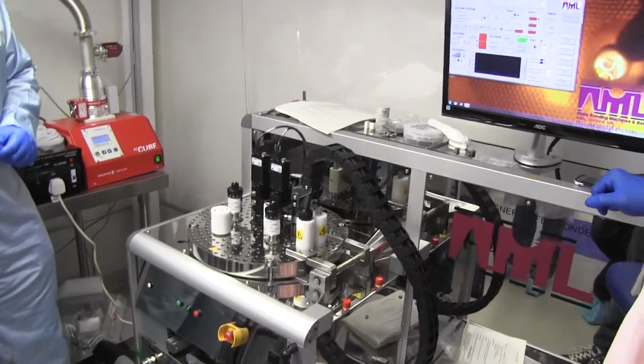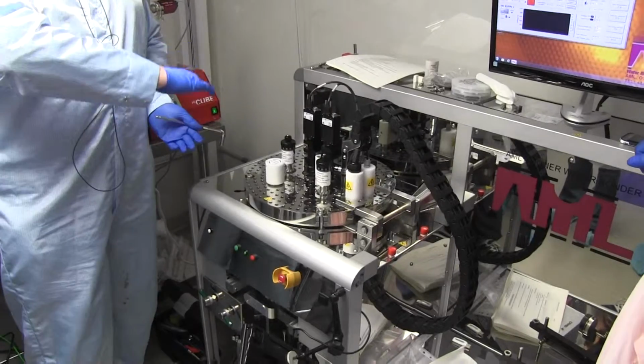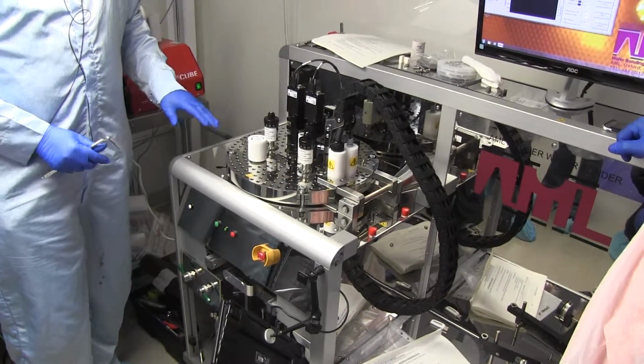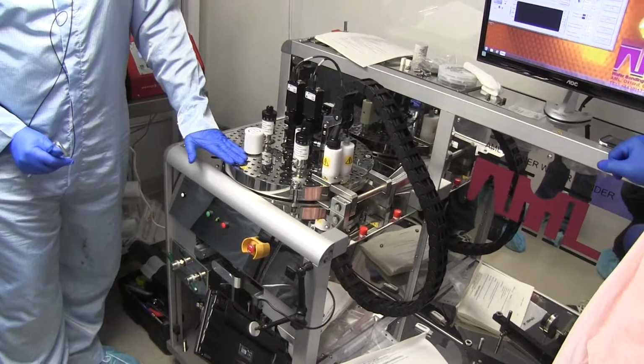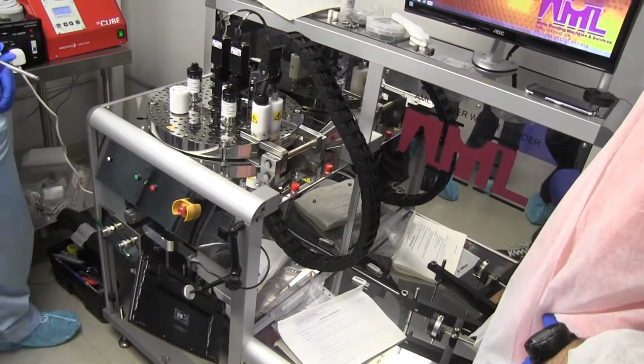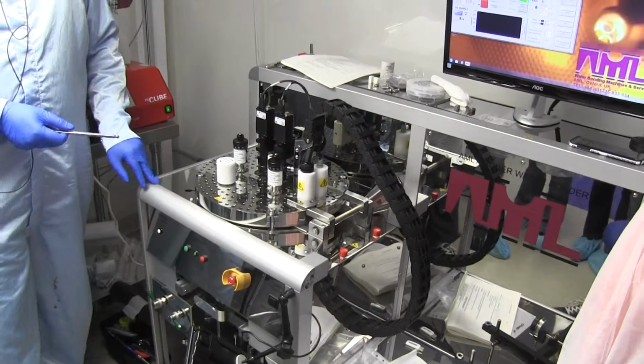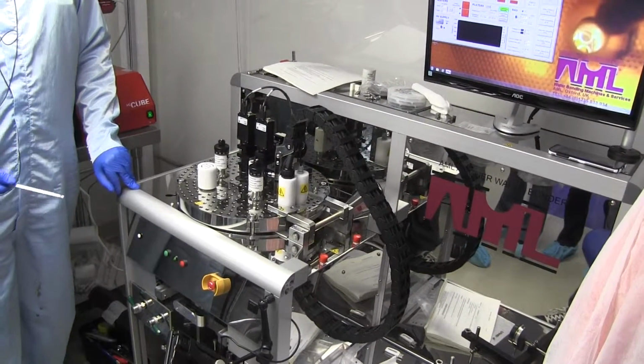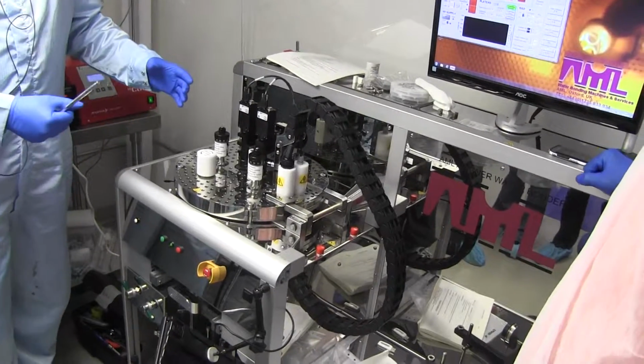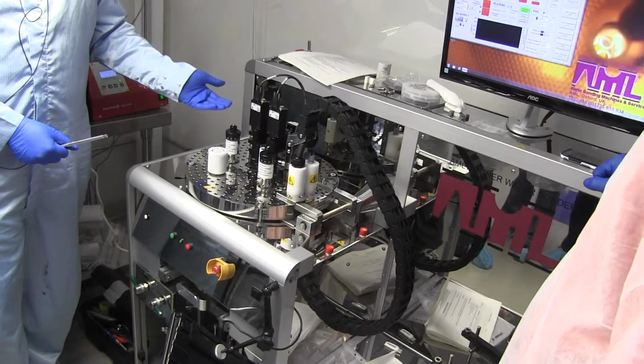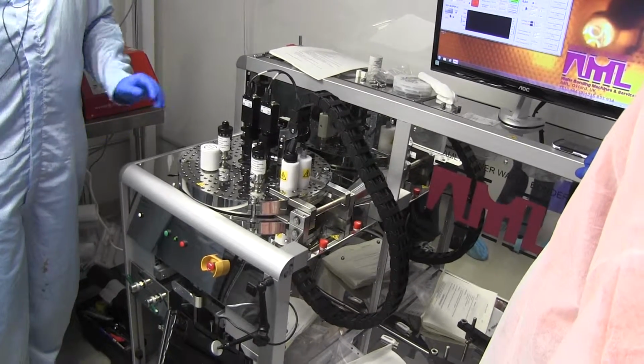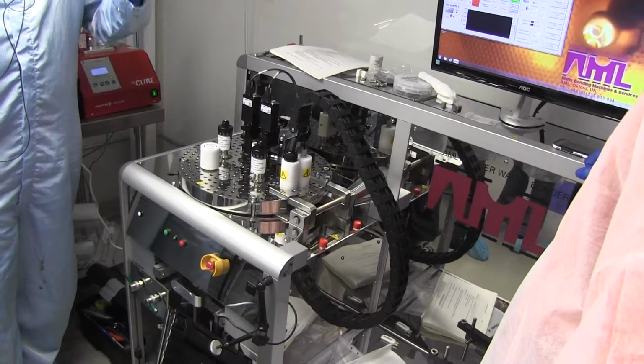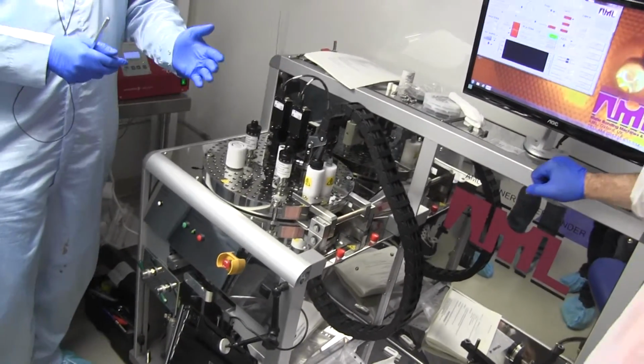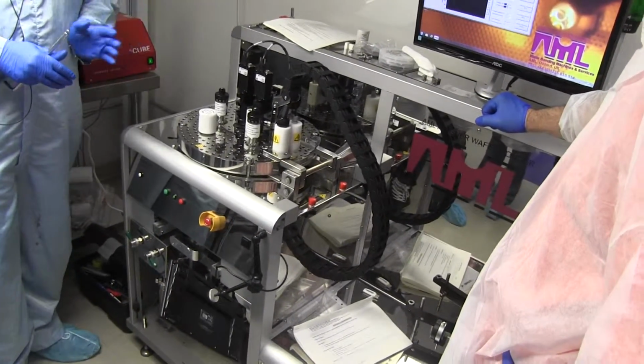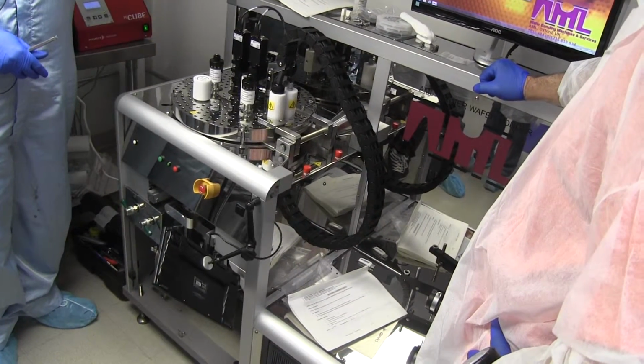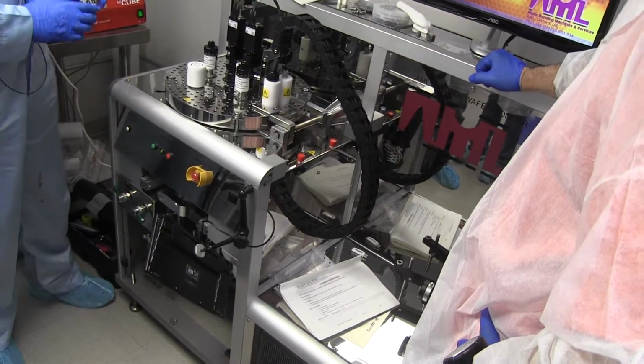So this is something we have to do during the bonding? After you've loaded the wafers, you'll close the lid, and you'll bolt these in immediately after that. That will ensure that the lid is pulled down flat. They also serve a second purpose: if we're applying high force for any reason, say a eutectic bond or a thermocompression bond, and you're applying 25 kilonewtons of force, it stops the lid from being pushed open. With that amount of force pushing up, if you didn't have them in, it would overcome the vacuum pulling down, open the lid, vent the chamber, and basically cause havoc to the turbo pump. So they're important to keep the lid sealed down when you're applying force.